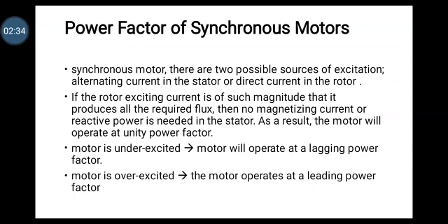Okay, next one, in case the rotor exciting current is greater now, the motor operates at the leading power factor. That means the motor is over excited. The excess flux must be counterbalanced in the stator itself. Now the stator usually absorbs the reactive power from the supply, but now the stator delivers the reactive power to the three-phase lines. That means it delivers the leading reactive power. Now the motor behaves like a source of reactive power, that is leading in nature, so it's like a capacitor. Now the motor operates at the leading power factor.